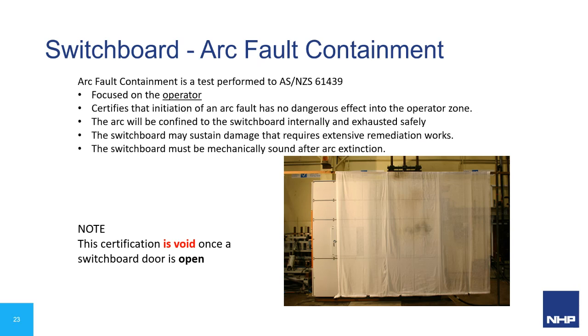Arc fault containment, you might have heard this one before. This is under 61439. I just wanted to explain the sort of testing that goes into this one as well. It's very much focused on the operator. This is actually our Cubic switchboard system under test. Basically they put this cheesecloth in front in the operator zone, as it's called. That's 30 centimeters away from the front of the switchboard. The idea is that an arc fault's initiated inside the board and this cloth should not be affected. Specifically, it's in front of the board.